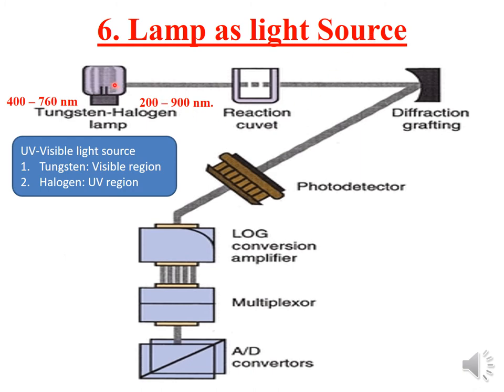Generally in the fully automated analyzer, we use a tungsten halogen lamp. The tungsten component is used for the visible range, and the halogen lamp is used for carrying out analysis in the ultraviolet region.